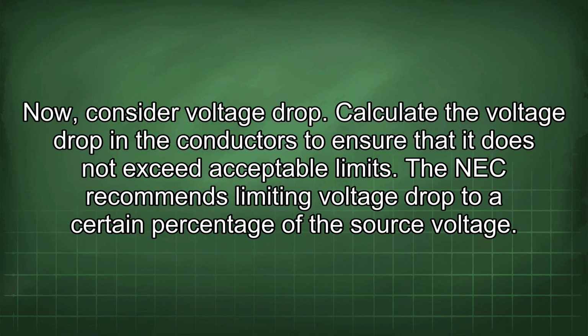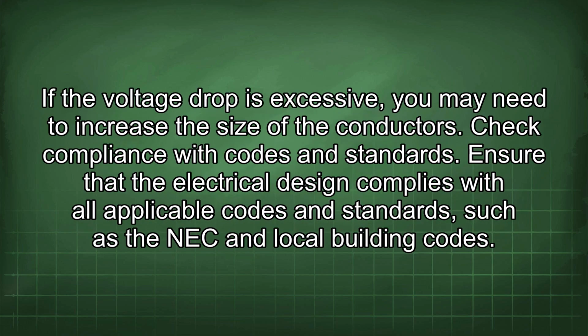Now, consider voltage drop. Calculate the voltage drop in the conductors to ensure that it does not exceed acceptable limits. The NEC recommends limiting voltage drop to a certain percentage of the source voltage. If the voltage drop is excessive, you may need to increase the size of the conductors.